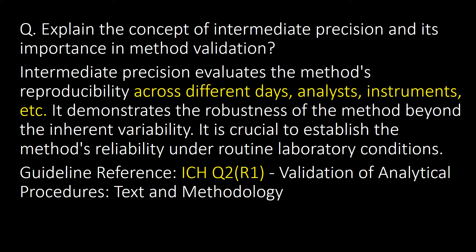Explain the concept of intermediate precision and its importance in method validation. Intermediate precision evaluates the method's reproducibility across different days, analysts, instruments, etc. It demonstrates the robustness of the method beyond inherent variability and is crucial to establishing the method's reliability under routine laboratory conditions. Guideline reference: ICH Q2.